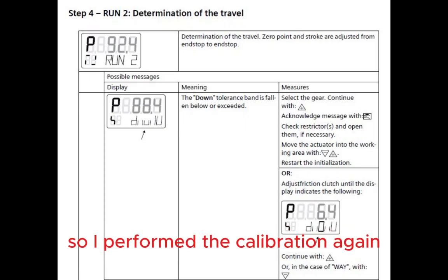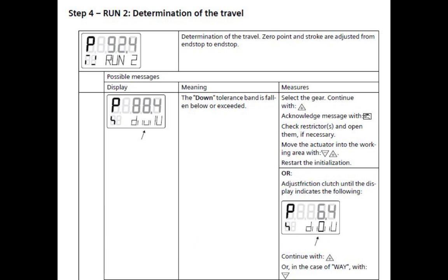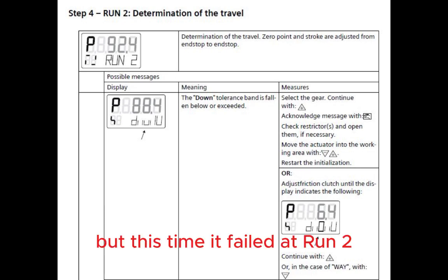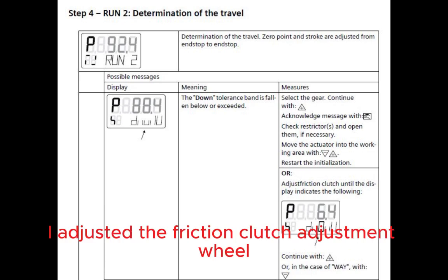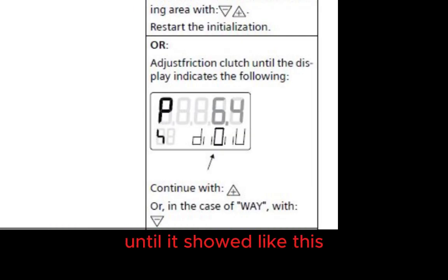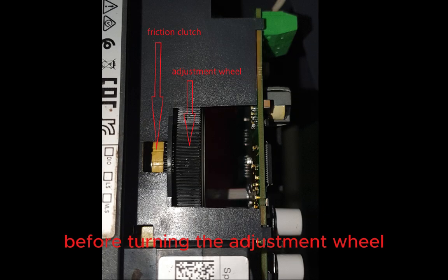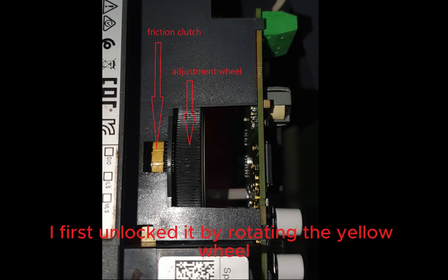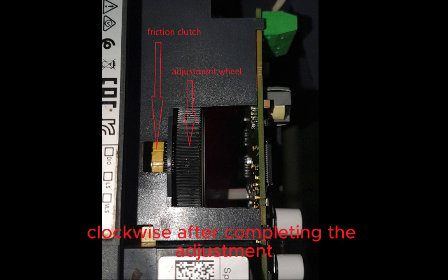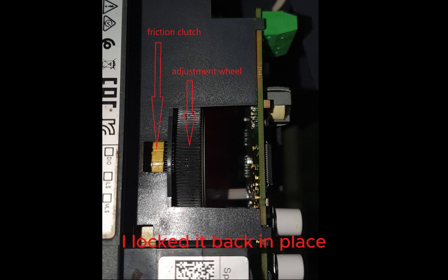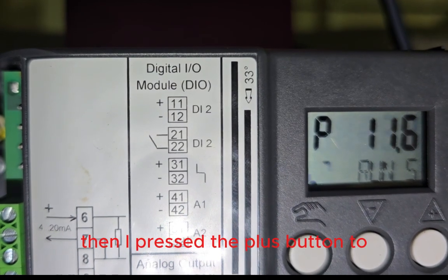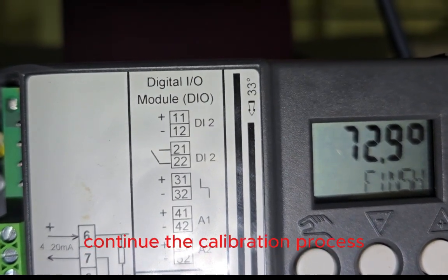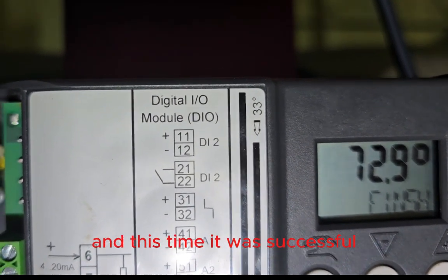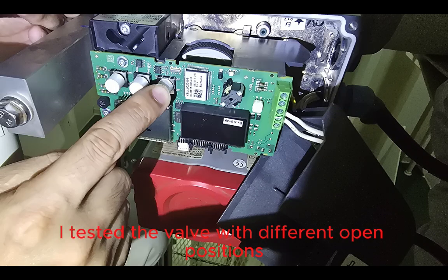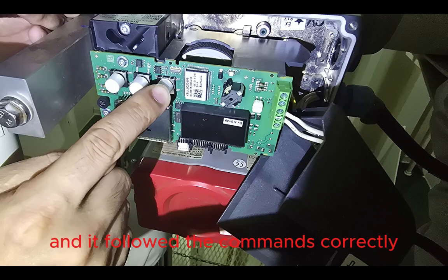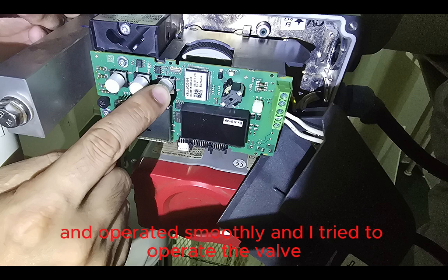So I performed the calibration again using the same procedure. But this time it failed at run 2. To solve this, I adjusted the friction clutch adjustment wheel until it showed like this. Before turning the adjustment wheel, I first unlocked it by rotating the yellow wheel clockwise. After completing the adjustment, I locked it back in place. Then I pressed the plus button to continue the calibration process, and this time it was successful. I tested the valve with different open positions, and it followed the commands correctly and operated smoothly.